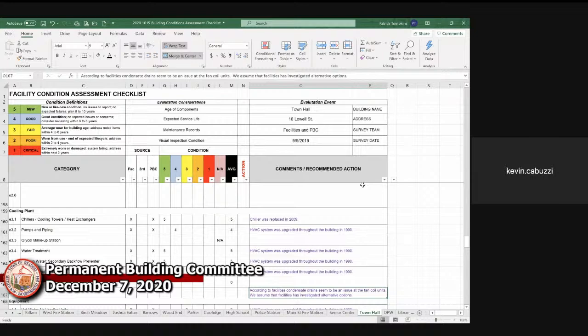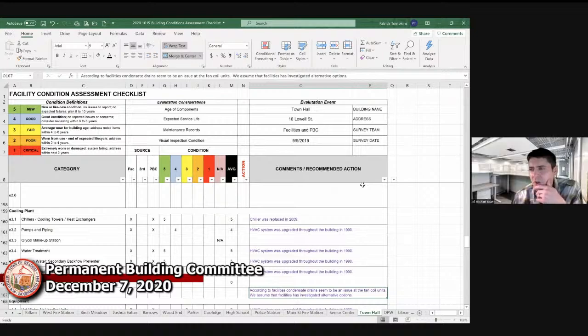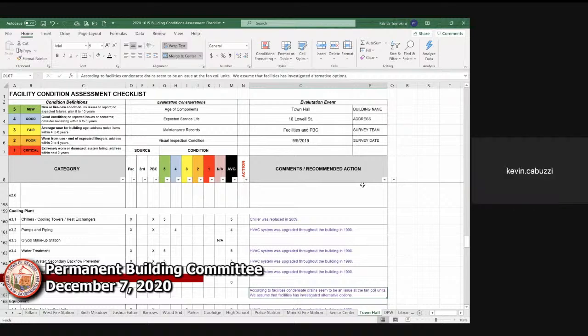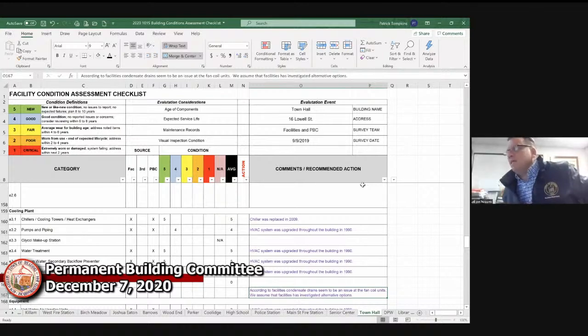Kevin or Joe, are there any issues with condensate pumps in that area? I have a note on mine. Some of the units in town hall, the building was kind of retrofitted for air conditioning, so those fan coil units scattered throughout the building, some have condensate draining by gravity, and some have condensate pumps inside the cabinet of the unit, individual little pumps like you'd see on the side of a residential furnace. Most of those are in the basement, the ones with the pumps.